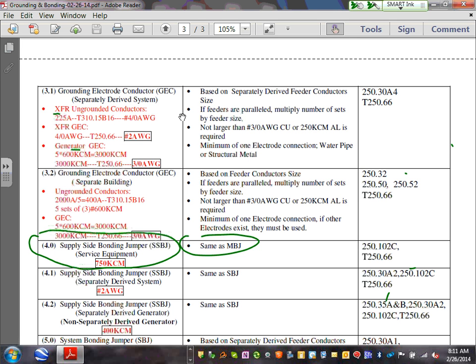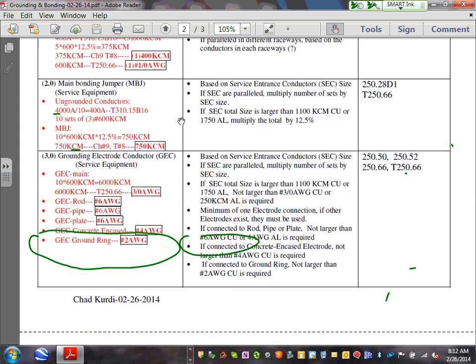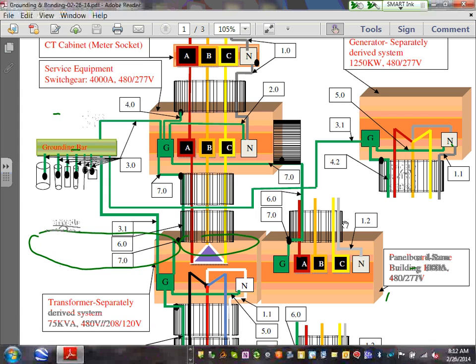Grounded conductor, main bonding jumper, supply side bonding jumper, and grounding electrode conductor. These are the fundamental building blocks of the grounding and bonding system at the service. They call it grounding and bonding at the service. Before I leave that topic and move to a different topic, guys, any comments, any questions about bonding at the service? The NEC sequence will call it bonding at the service. Can you see all the stuff that I just talked about was right here at the service. Bonding and grounding at the service. Four things: grounded conductor, main bonding jumper, grounding electrode conductor, and supply side bonding jumper. Four things you have to do at the service.